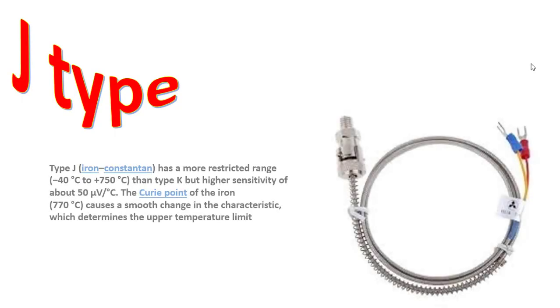Type J has a more restricted range of -40°C to +750°C than Type K, but has a sensitivity of about 50 µV per °C. The Curie point of iron at 770°C causes a smooth change in the characteristic, which determines the upper temperature limit.